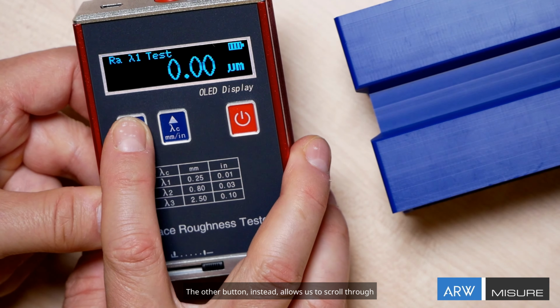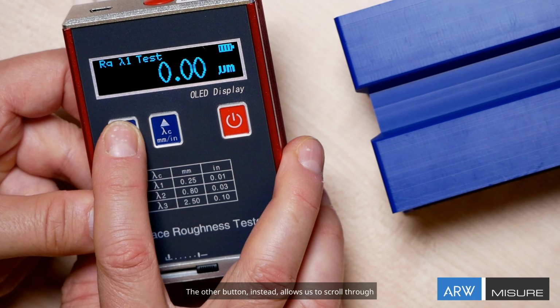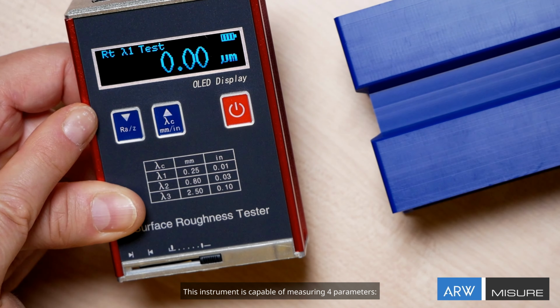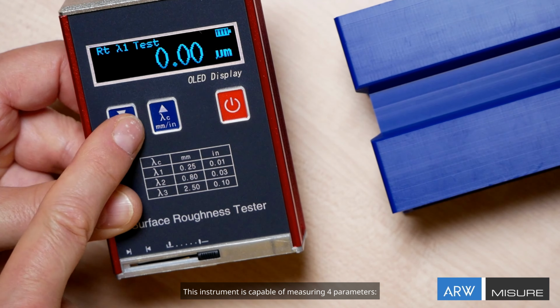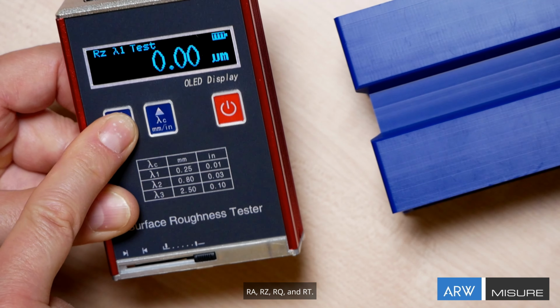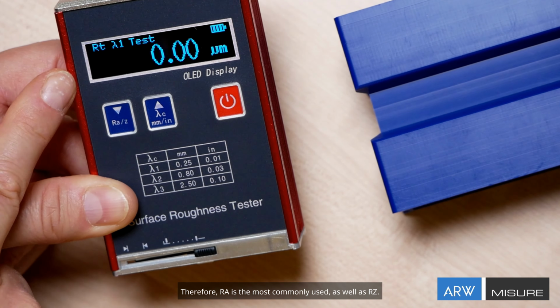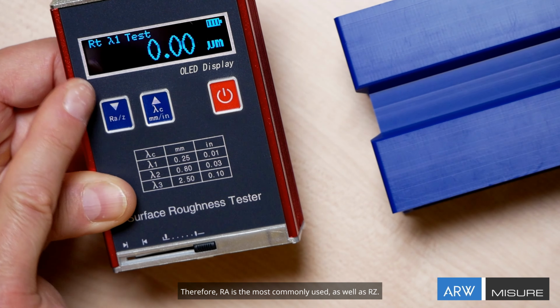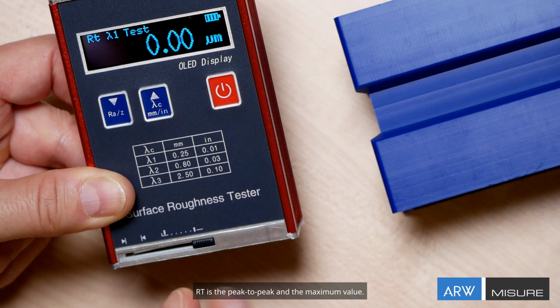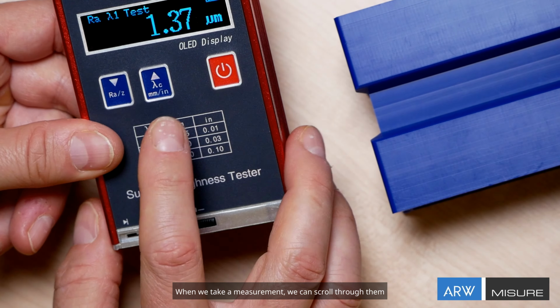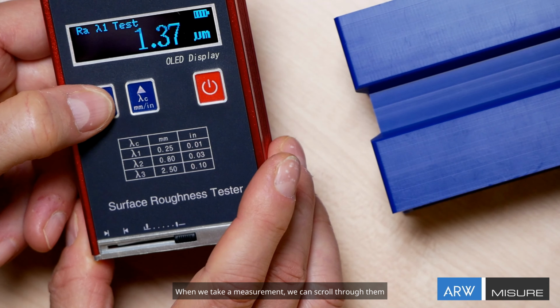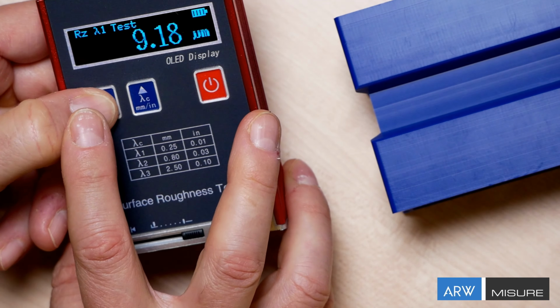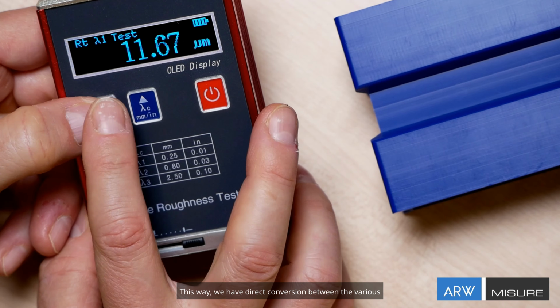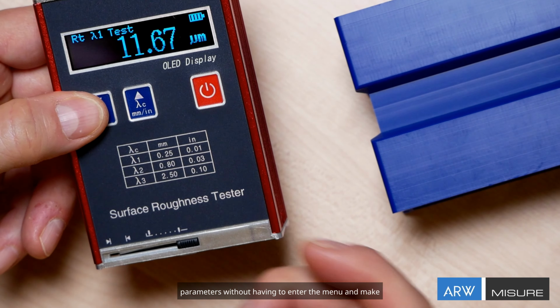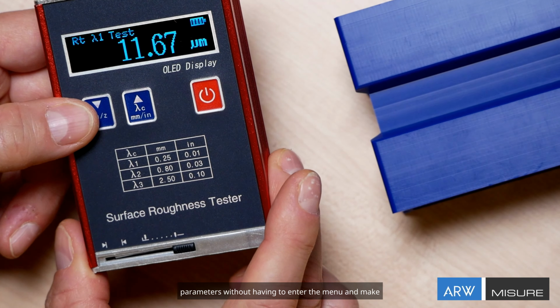The other button instead allows us to scroll through 4 parameters. This instrument is capable of measuring 4 parameters: RA, RZ, RQ, and RT. Therefore, RA is the most commonly used, as well as RZ. RT is the peak-to-peak and the maximum value. When we take a measurement, we can scroll through them directly. RA, RZ.